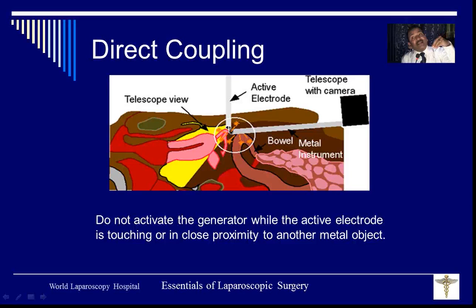Even if your cannula is very near the target of dissection and the tip of your Maryland is touching the tip of the cannula, it can take the current to the cannula and it can burn the bowel. Just like when one person is getting a shock, if you try to catch that person with bare hands, you are also getting shocked. In movies they exploit this a lot in comedy. So what you should do is use wood or something to hit him to remove it. Otherwise, this is called direct coupling, where the current of one instrument goes to another and burns the bowel.